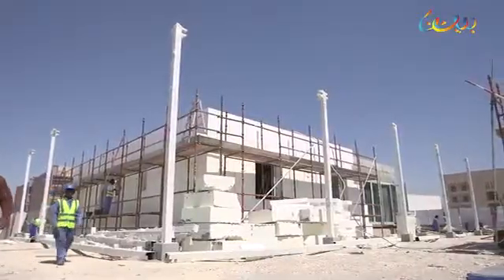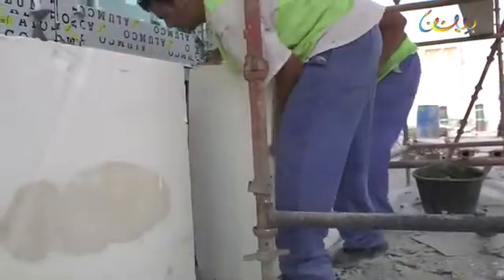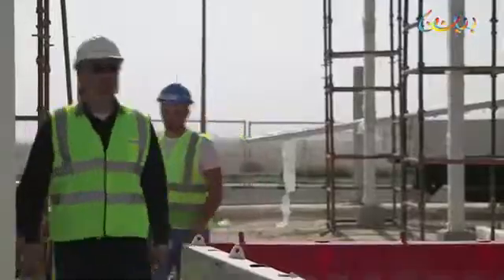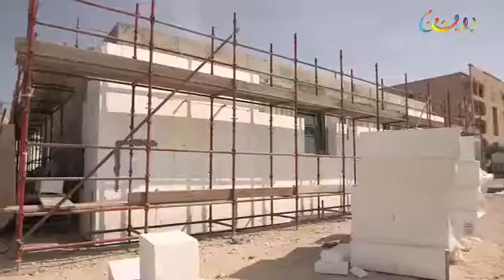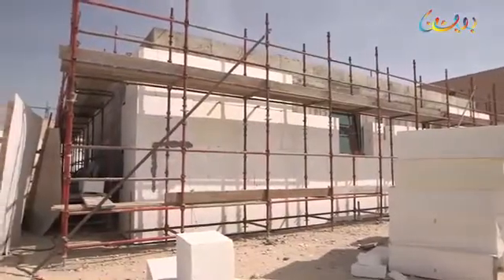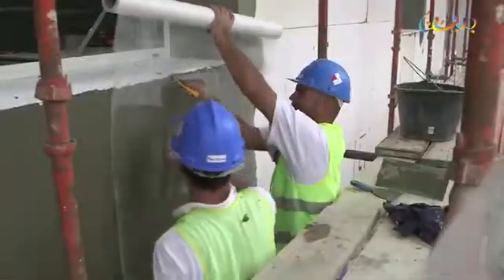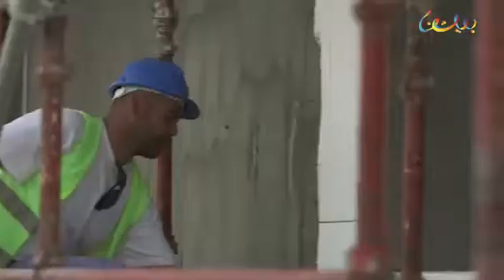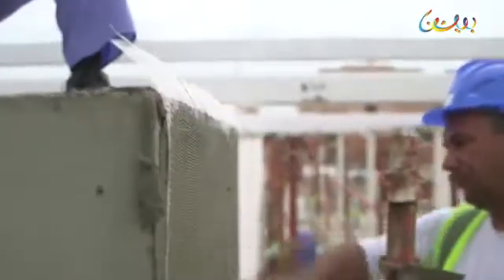In the passive house, the insulation goes all over the house. So you have an envelope, which is practically sealing the house in. The second difference is the thickness. Normal insulation is a couple of centimeters thick, 3, 4, 5 centimeters. Here the insulation is 38 centimeters. So it's a very, very thick material, which grants good thermal isolation. What is very important here is to close it really airtight so that you have no thermal bridges, that you're not losing energy anywhere, that no heat or cold is getting out or getting in, which is not controlled.